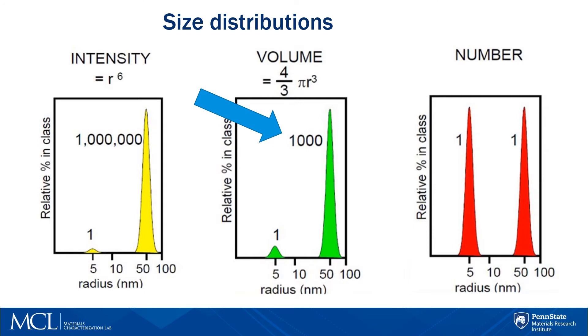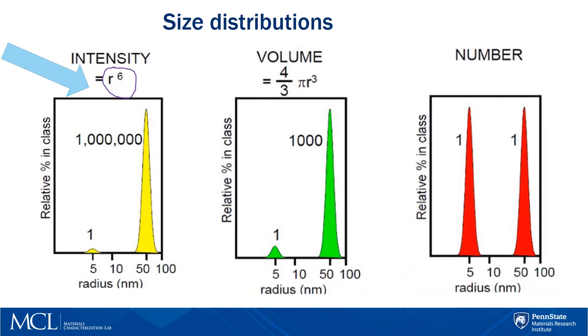For DLS, we normally report size distribution by intensity. Note that intensity is proportional to the radius of the particles to the power of 6, so this technique is very sensitive to the presence of larger particles or aggregates.